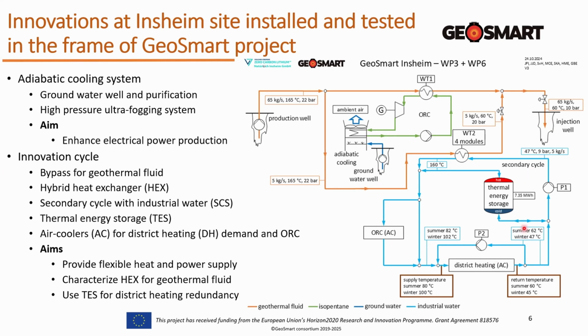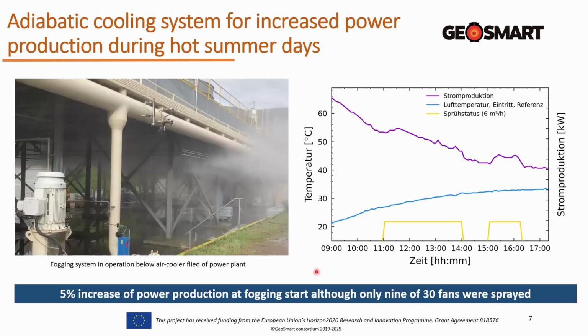So first, for the adiabatic cooling system: here in the picture we can see the system in operation. Basically, these are the little lines under the air-cooled condenser where we spray water, which you can see here as fog, and this then vaporizes on its way to the cooling fins of the air-cooled condenser.